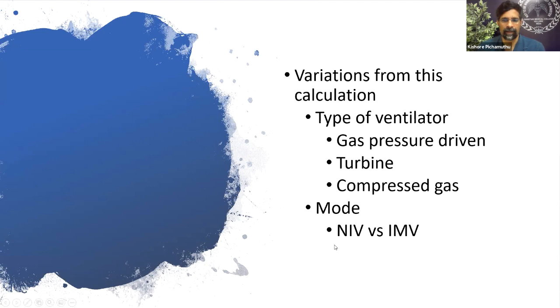In the last 5 years or so, almost all new models of ventilators launched are turbine-based, and these tend to consume a little bit more oxygen than the standard compressed gas ventilators, where the ventilators operate by having a reservoir of compressed oxygen and air and mixing it and sending it through. So that's a usual ventilator that we see in the ICUs, the compressed gas. The newer ones are turbine-based. And the turbine-based ventilators have sometimes almost up to 10 liters per minute more oxygen consumption than the standard older model of ventilator. We must remember that ventilators can be used as NIV as well. So if you're in an NIV mode of ventilation, this calculation may not be very accurate. And leak flow compensation, of course, is much more in NIV as well. So the mode may also affect the oxygen consumption calculations.